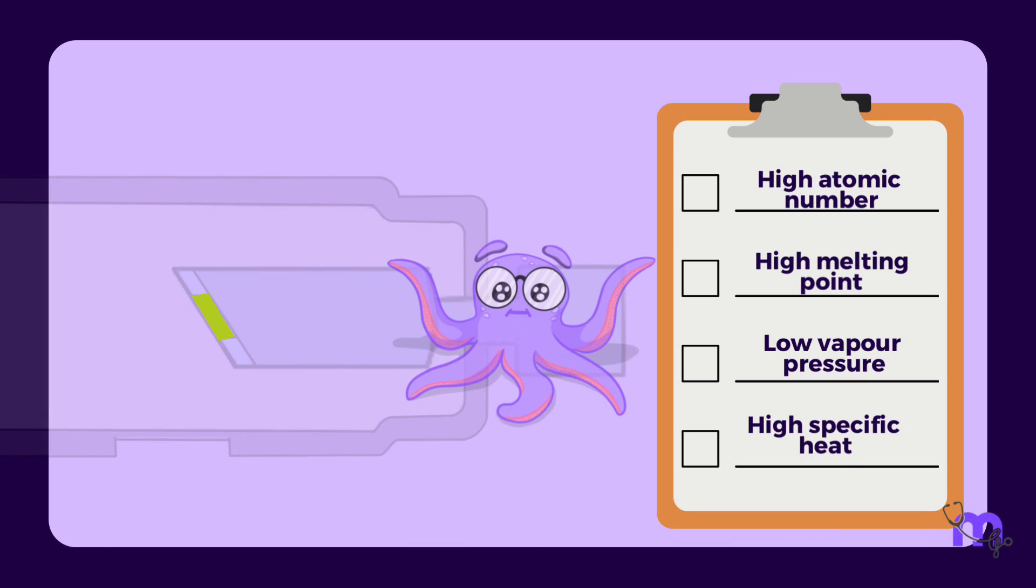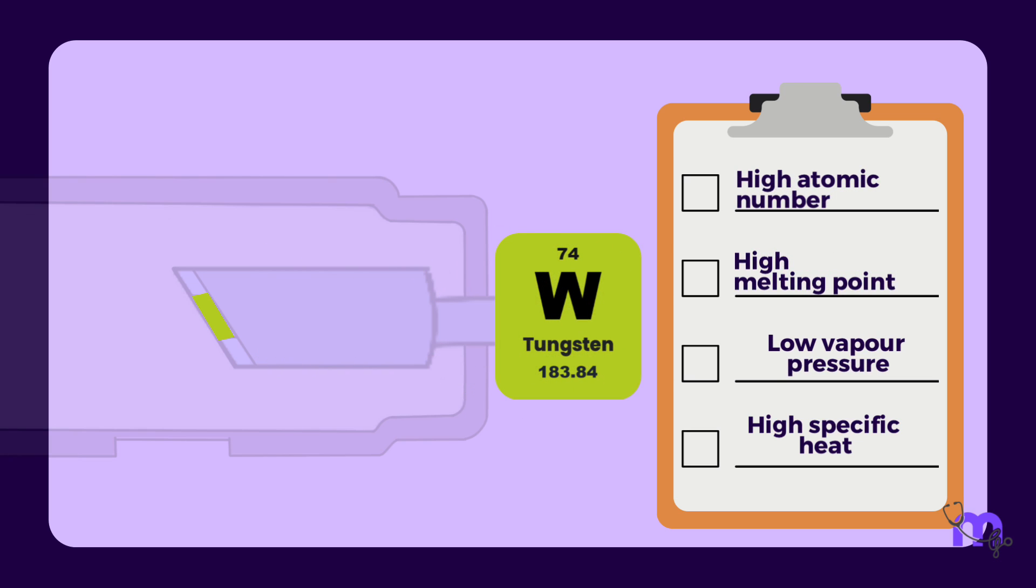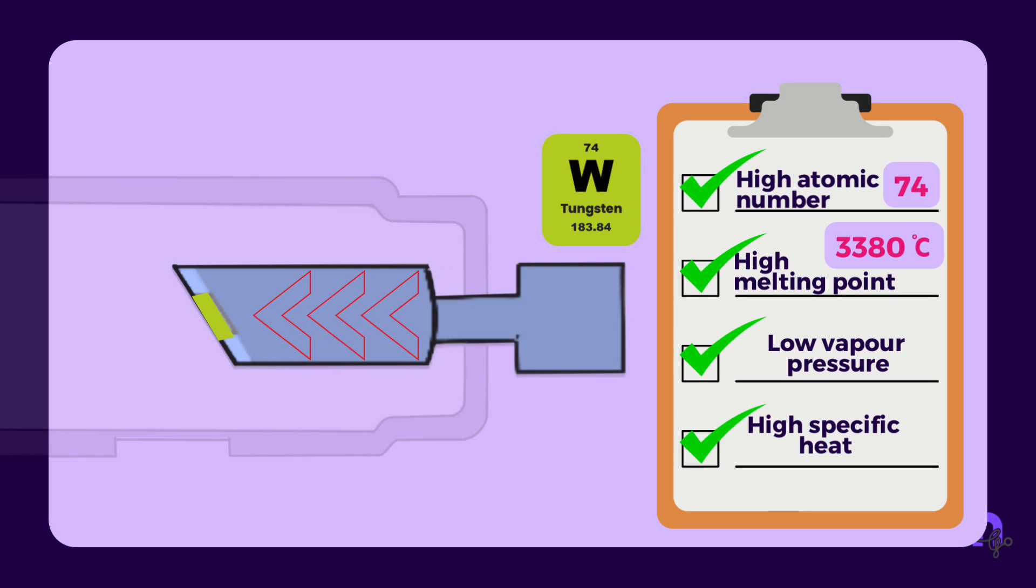So how does tungsten become our ideal target material? Tungsten has a high atomic number, that is 74, a high melting point of 3,380 degrees Celsius, and a low vapor pressure. The only criteria that it does not meet is that of having a high specific heat. To compensate for this, the tungsten target is embedded in a copper block, which is a good thermal conductor.